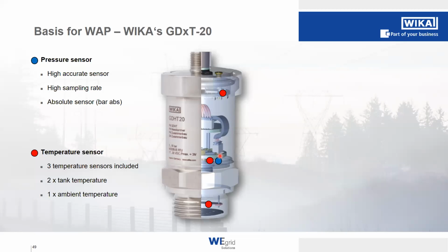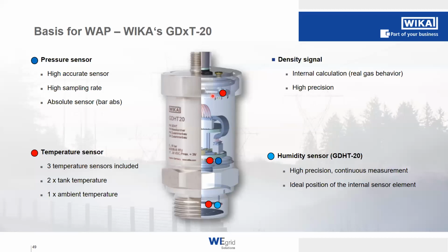In addition, we have 3 temperature sensors included in this one GDHT. 2 sensors measuring the tank temperature, one here, one here, and 1 sensor measuring the ambient temperature. That means we are able to have a proper measurement of temperature, and we can account for changes in the environment temperature, because they are moving faster than the temperature change inside the gas compartment. Then, out of these sensors, we can calculate the density, basically. This is an internal calculation that is done on the PCB of the sensor based on real gas behavior. And this calculation can be done with a really high precision.